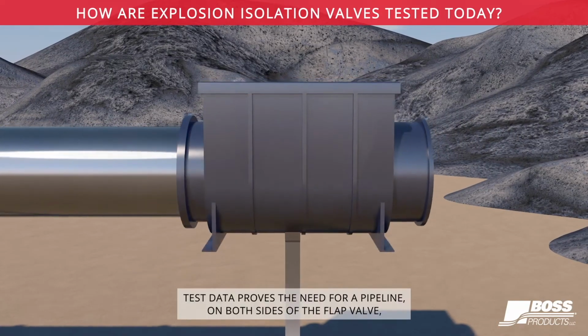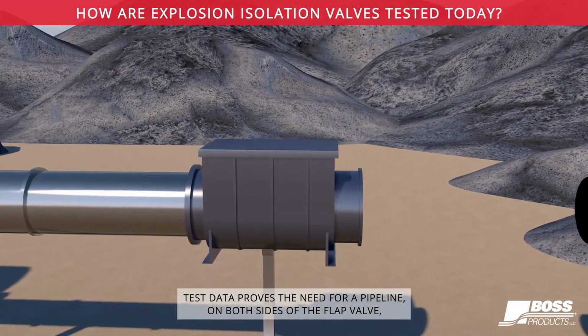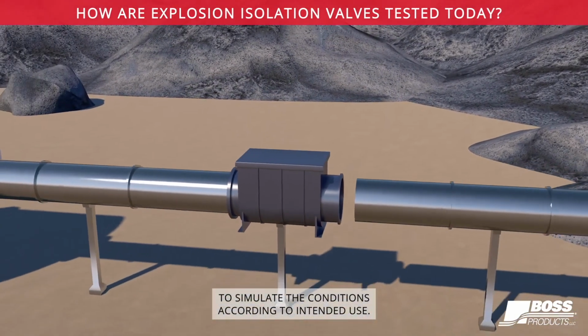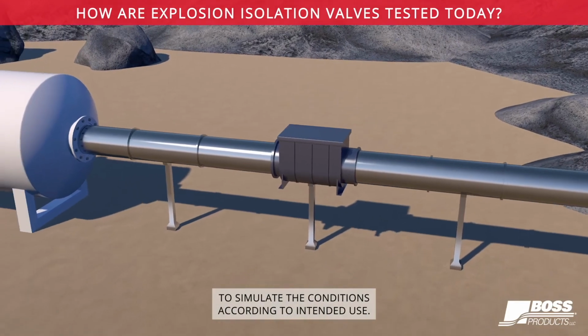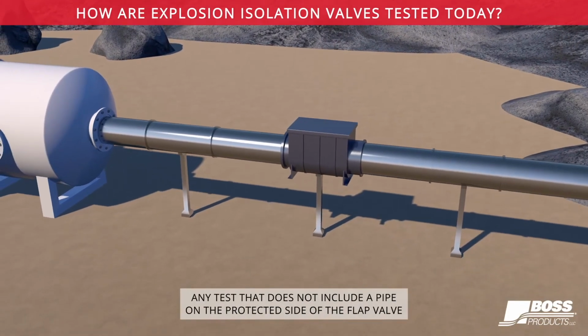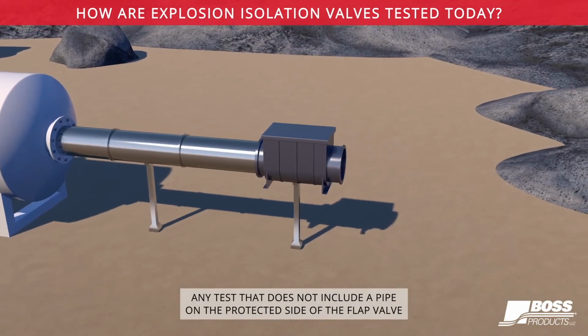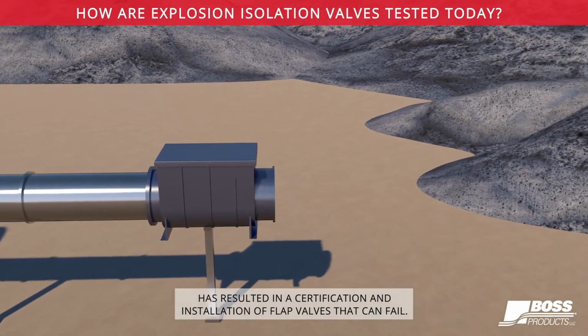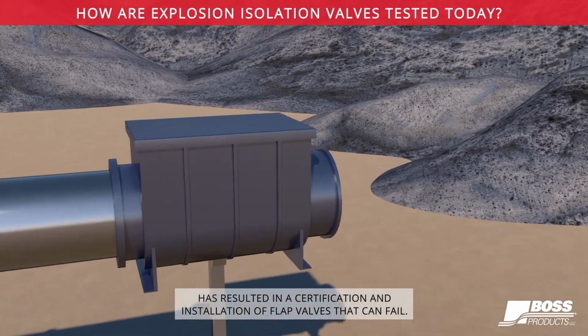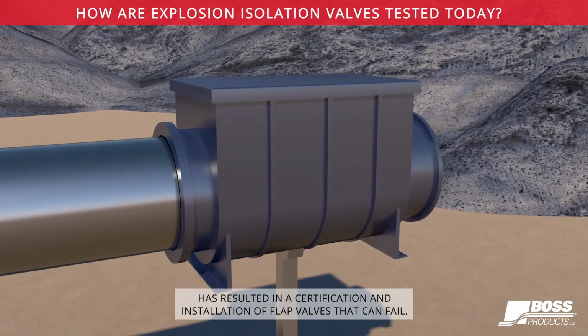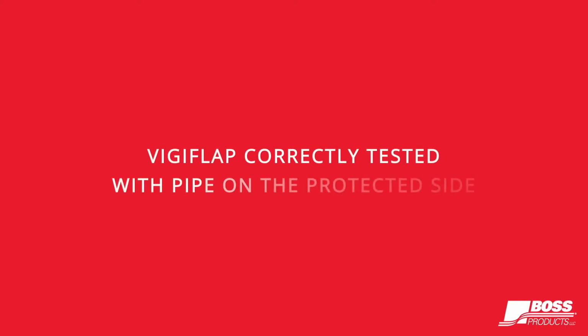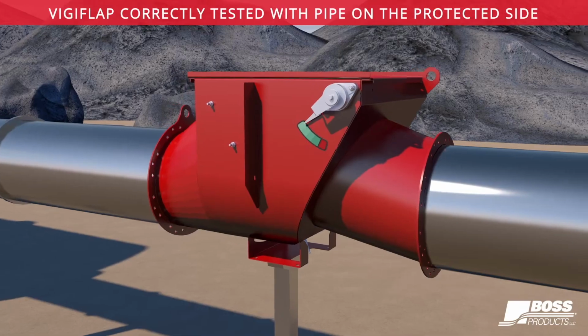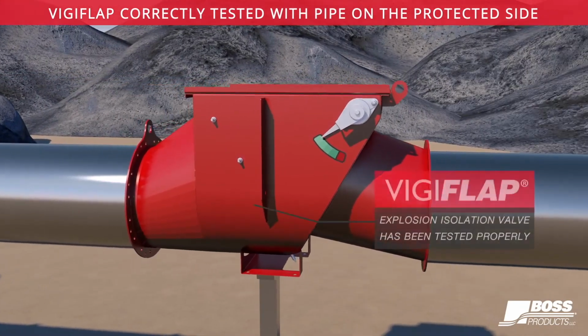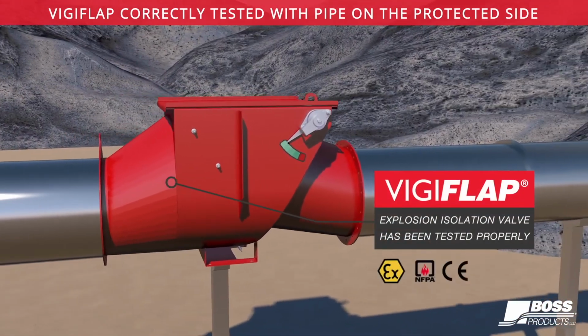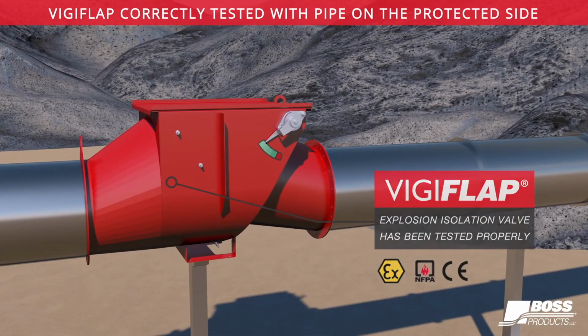Test data proves the need for a pipeline on both sides of the flap valve to simulate the conditions according to intended use. Any test that does not include a pipe on the protected side of the flap valve has resulted in a certification and installation of flap valves that can fail. So how we test our VigiFlaps is we put both sides of the pipe together, because what it's going to explain is there's going to be pressure on both sides when an explosion happens.